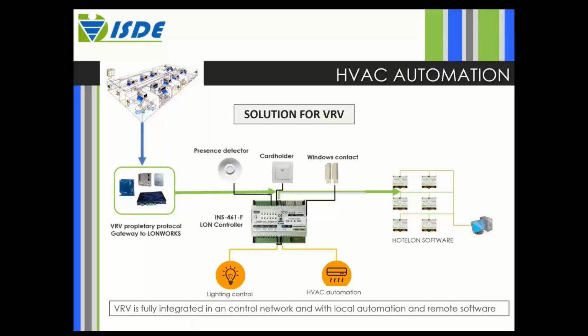Next, most VRV systems implement a proprietary protocol to communicate with the terminal units. As market and client demand it, they also offer a gateway to a standard protocol like LonWorks. So if we add this gateway to the system, once we're speaking the same language, we can automate the HVAC system by adding a LonWorks device like the INS 461, which is capable of adding presence elements to the system like presence detectors, card holders, and window contacts. This provides the algorithm to maximize energy efficiency.